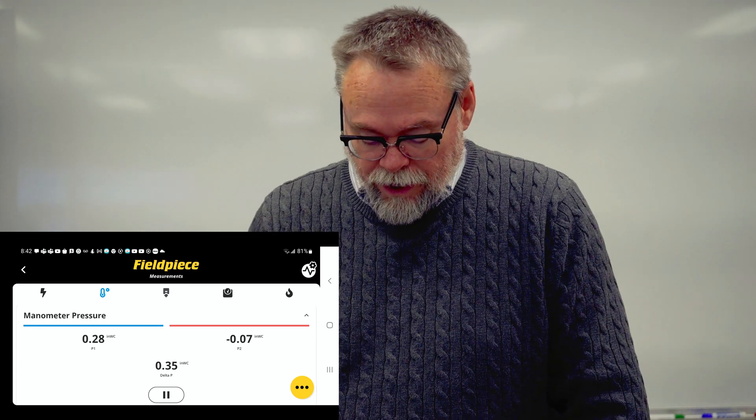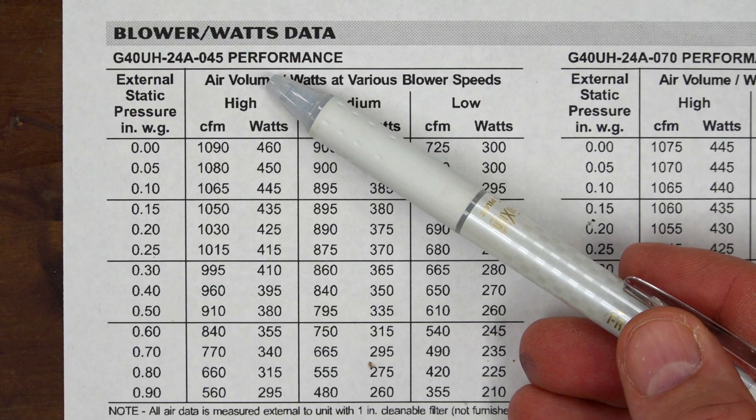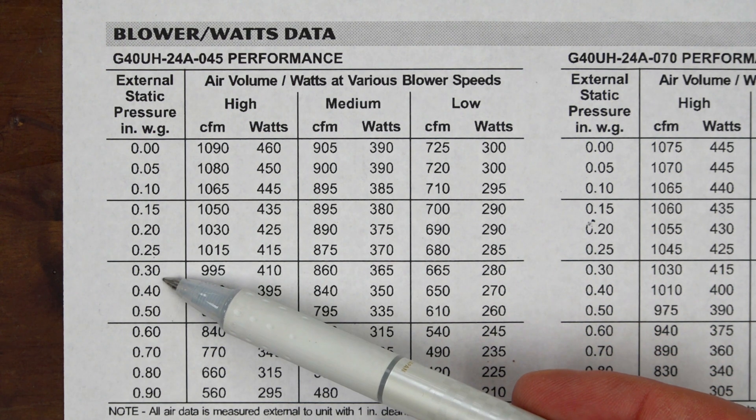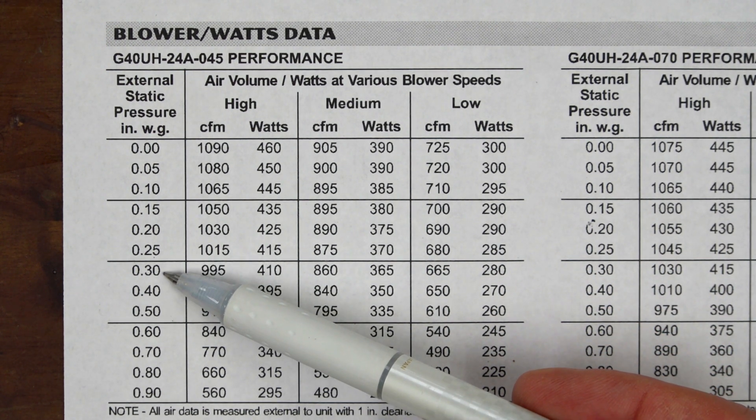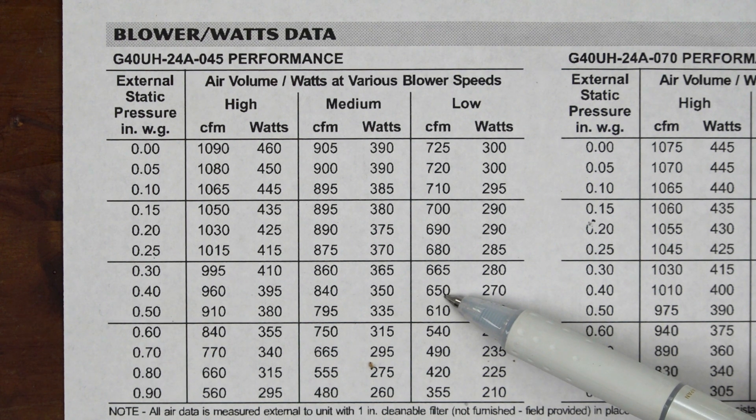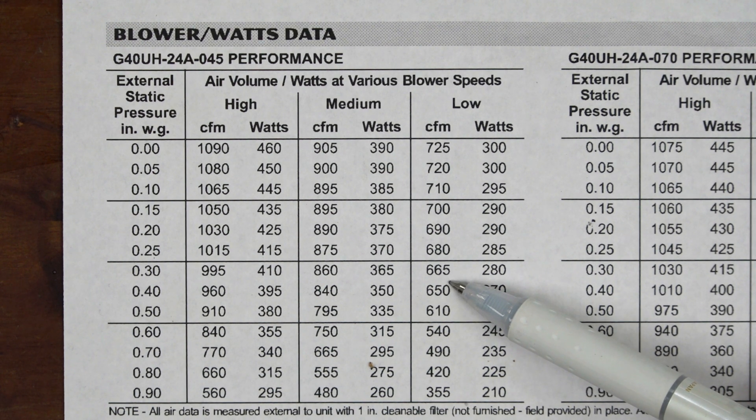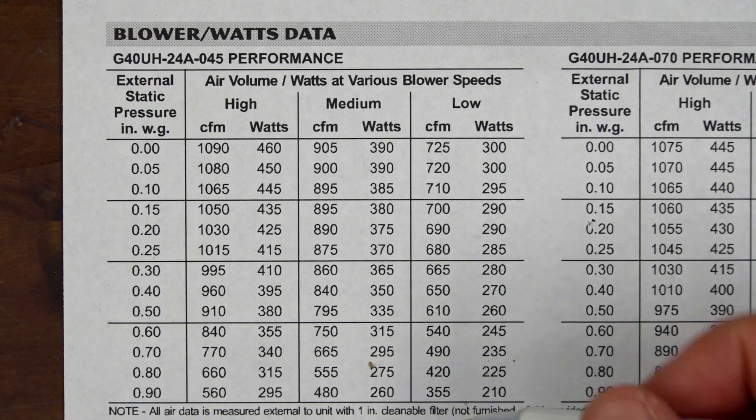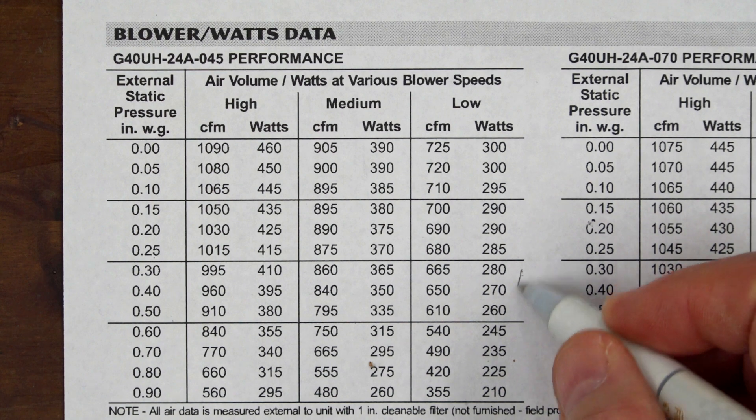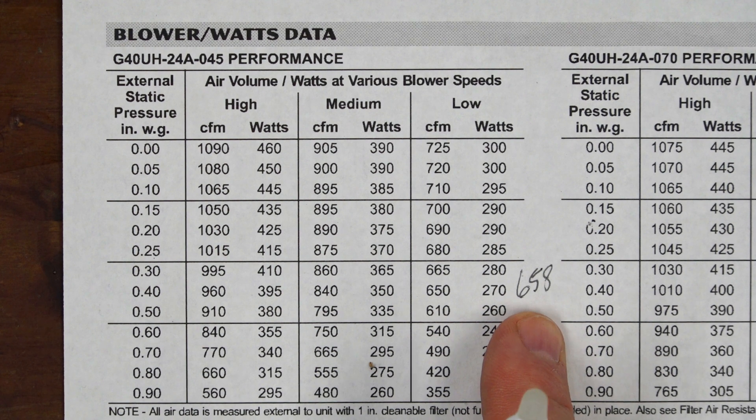If you take a look at, this is the blower tables right here. This is the G4024A45. This is this particular furnace. What we want to do is we want to go down to our static pressure, external static pressure, which is 0.35, which is right in between 0.30 and 0.40. And we know it's on low speed. So we come across and at 0.3, it's 665. And at 0.40, it's 650. So we're going to cut that in half. We're going to make this about 658 CFM, somewhere in between here. Let's plug in an estimated 658 CFM. So 658 is what we're going to use for our CFM.